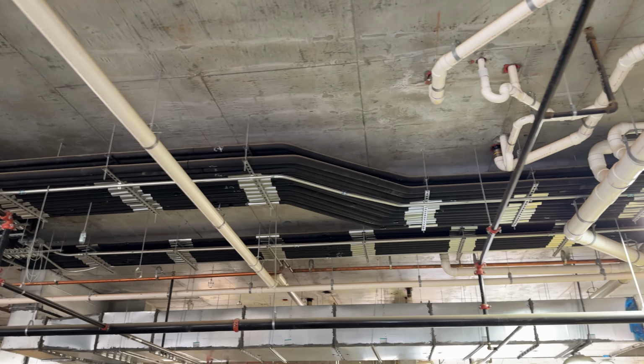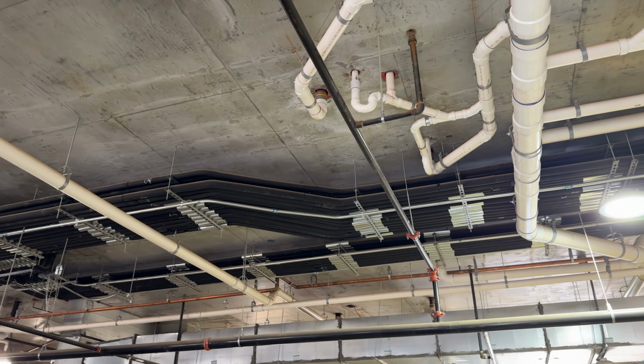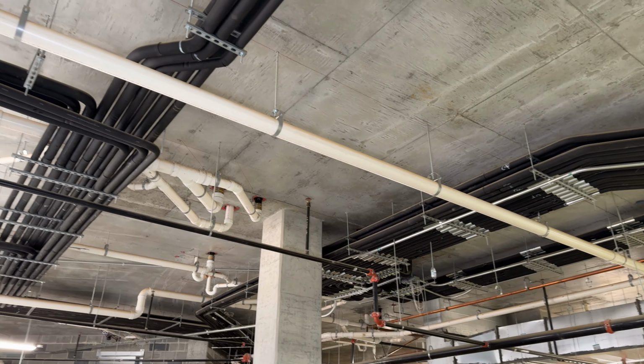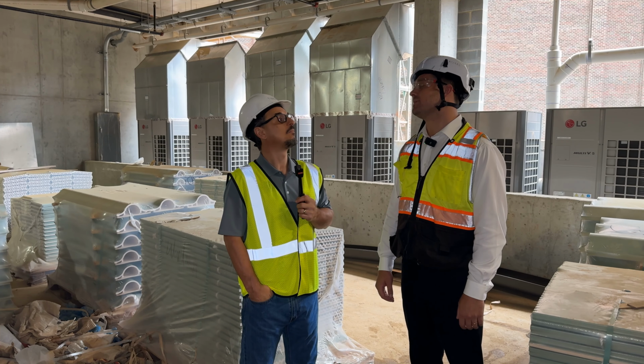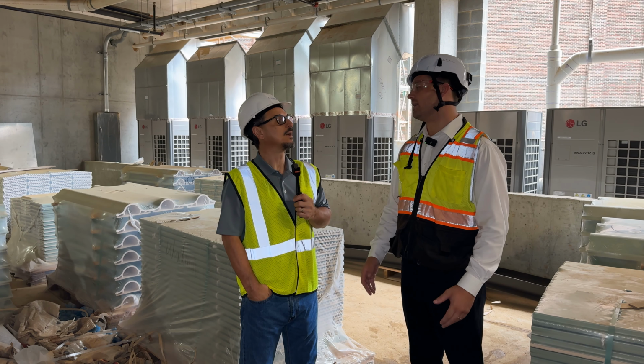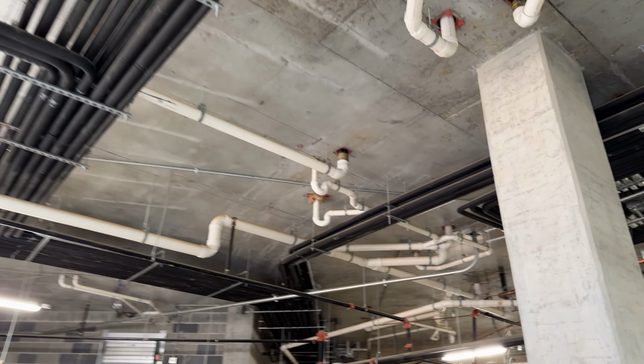It is. Yeah, you'll see that we use saddles here for hangers. That's to prevent the pipes from sagging over time. We don't clamp the pipes either. A lot of our work is investigating other folks' VRF installs, and a common pitfall that we see is people clamping down the refrigeration pipes, which then don't allow for expansion. Right, you need to let them have a little room to breathe, because they change with temperature.